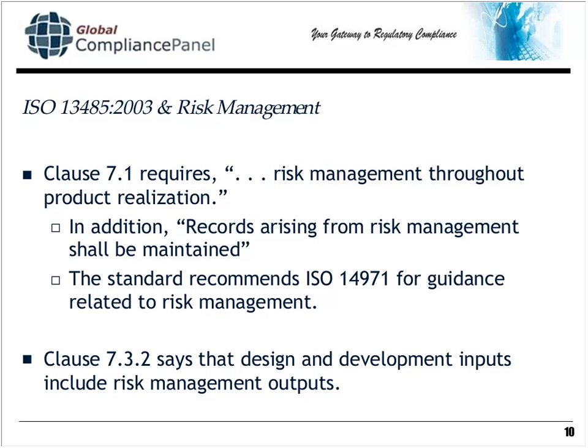Every time you do something to reduce the product risk, the medical device risk, that is going to produce an output from the risk management process, which is going to double back in as an input into the design control process. And so this is going to be one of the ways in which these standards get linked.